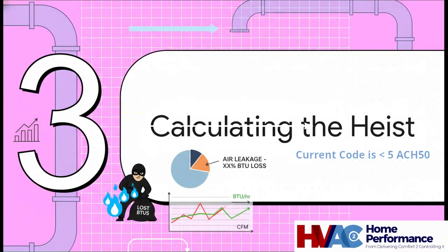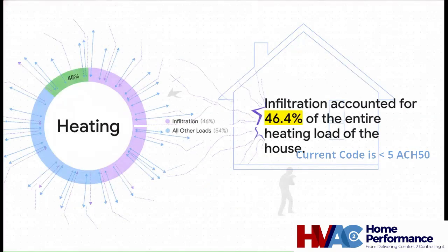So, with the break-in confirmed, it was time to calculate the exact value of what was being stolen. We have to translate that air leakage number, those CFMs, into the language of our industry, BTUs. And this chart just lays it all out, plain as day. Look at that massive slice.